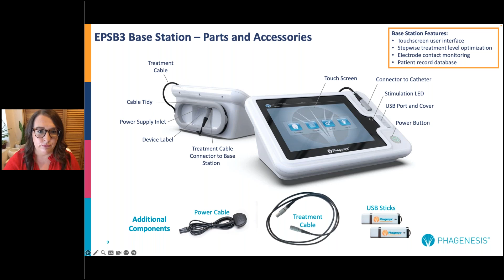Okay, so putting it all together, we have the Phagenesis system. So it's a dual function catheter. It's a treatment catheter that has 2 parts and 2 functions. So treatment catheter for delivery of pharyngeal electrical stimulation, but it also has that dual function where the inner core is an 8 French nasogastric feeding tube. Once the catheter is placed on day 1, it remains in place for the treatment duration. But it can be left in place even after treatment is complete if the healthcare provider still needed to use it to deliver enteral feeding for up to 30 days.